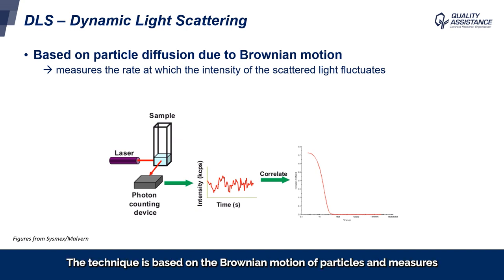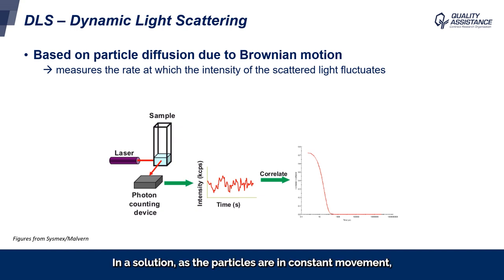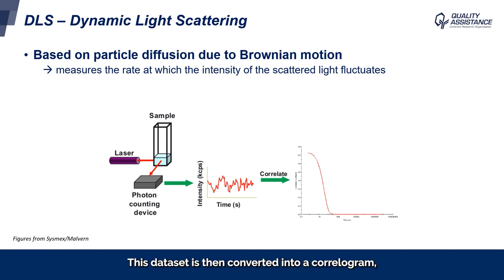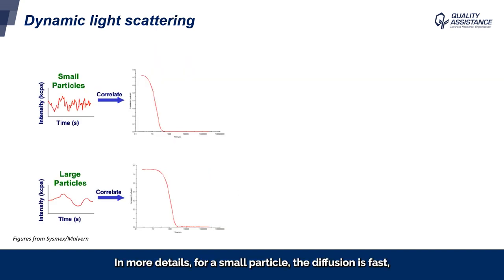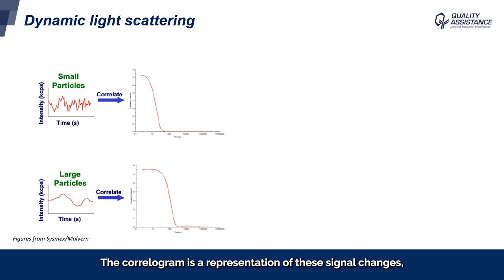The technique is based on the Brownian motion of particles, and measures the speed at which the particles are diffusing in the solvent. Particles in suspension are illuminated by a laser, and the particles will scatter some of the light that hits them. In a solution, as the particles are in constant movement, the light scattered by the particles is fluctuating over time — it is dynamic — and the light intensity as a function of time is what is measured. This data set is then converted into a correlogram, shown in the figure on the right of the slide. For a small particle, the diffusion is fast, which means more fluctuations of the intensity as a function of time than for a large particle moving rather slowly, as shown in the figures on the left.